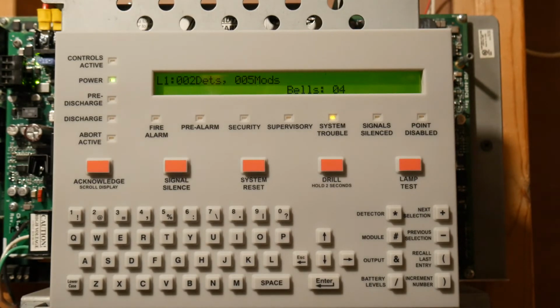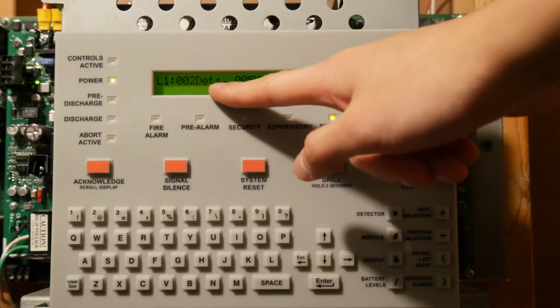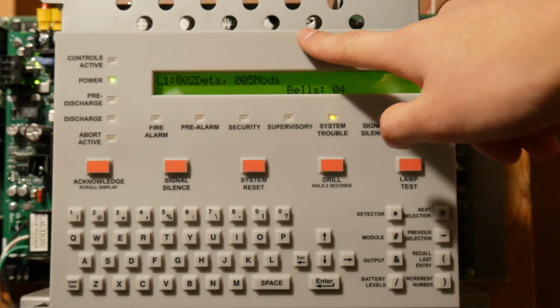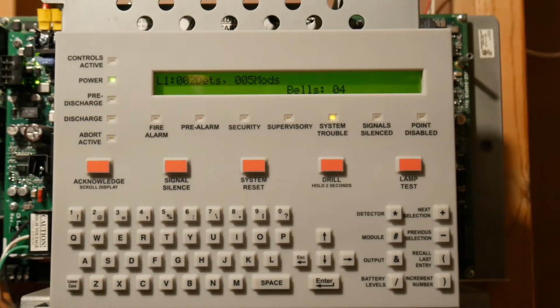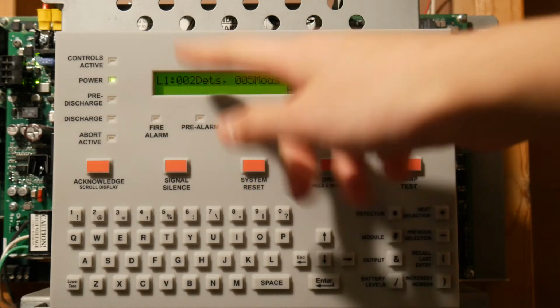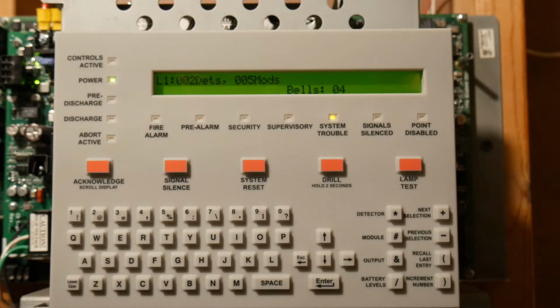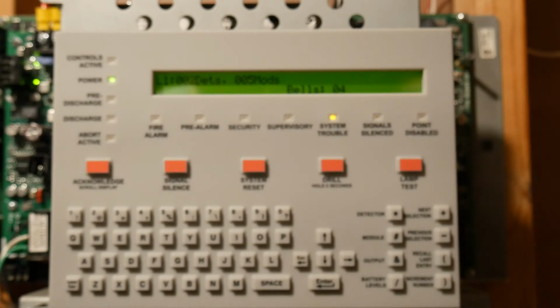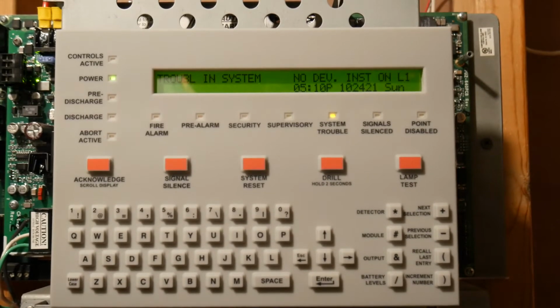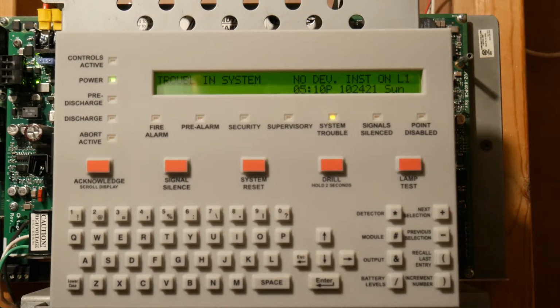Okay, it's done auto-programming. After it's done, it should show a screen like this. It says 2 detectors, 5 modules, and 4 bells. If it doesn't show this, that means there's probably nothing in the SLC. It depends. For example, if you don't have anything installed, it'll just show 4 bell circuits. If it does not show 4 bell circuits, that means something's wrong with your panel, because it should always show 4 bell circuits since there are 4 NACs in the panel.